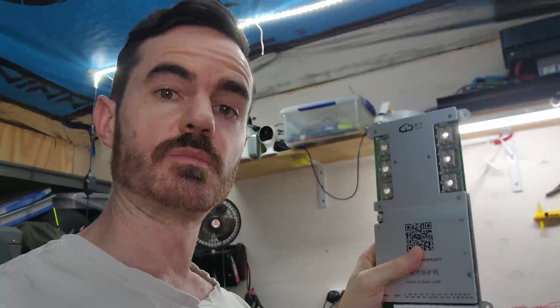As you can see, this JK BMS has 3 terminal connection points on it. Considering I'm going to be running up to potentially 300 amps, what I'm using is 3 times 5 AWG cables. These have a 200 degrees Celsius silicone coating around them too, meaning they can handle really high temperatures and extra current. So with all 3 of those together, it should easily be able to handle 200 to 300 amps.